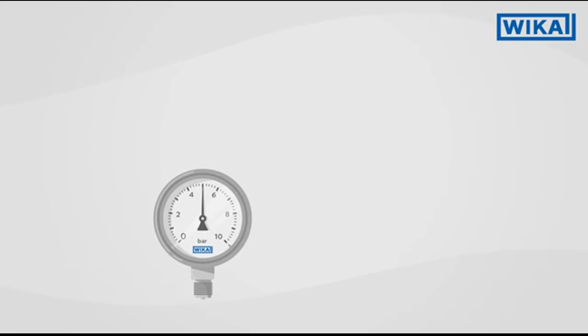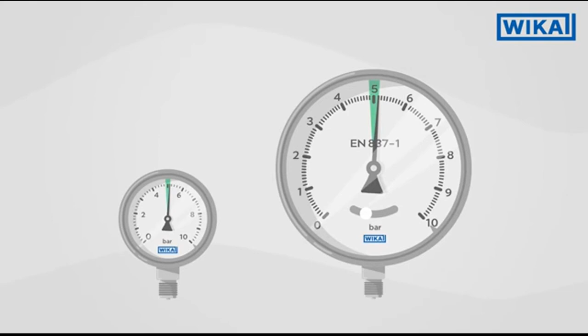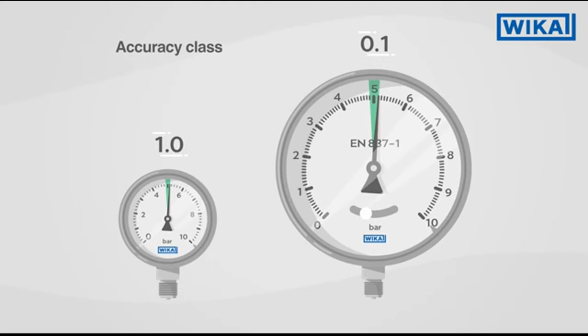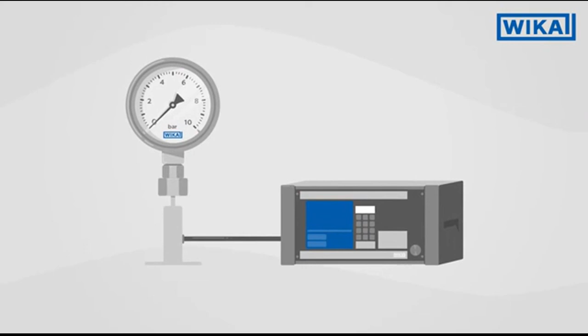With a calibration, the measuring instrument, also known as the calibration item, is compared with a reference measuring instrument. In this way, possible deviations are detected. The reference measuring instrument is more accurate than the measuring instrument and is traceable. Consider the calibration procedure using the example of a pressure gauge. The calibration is carried out over the entire measuring range. The 0 point, intermediate values, and the full scale value are checked.